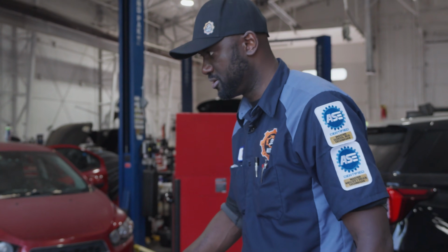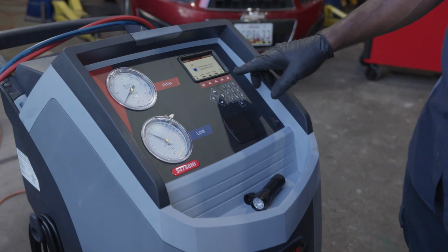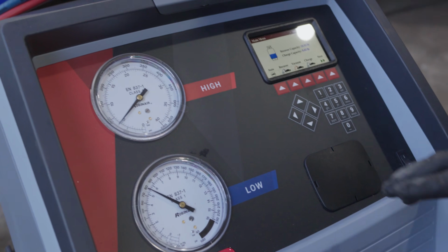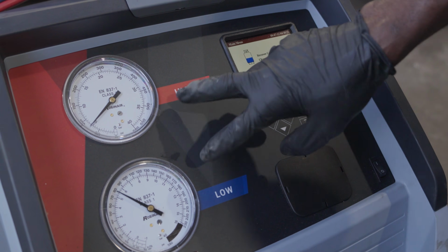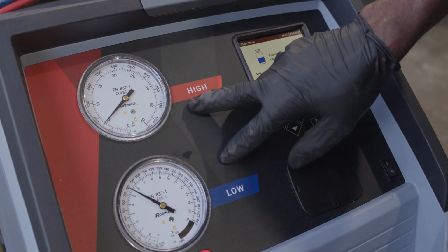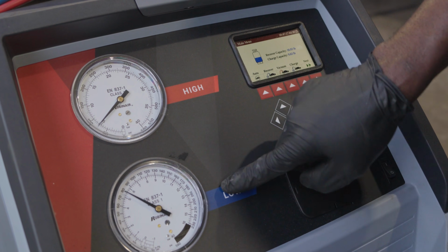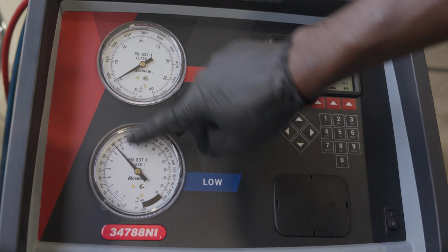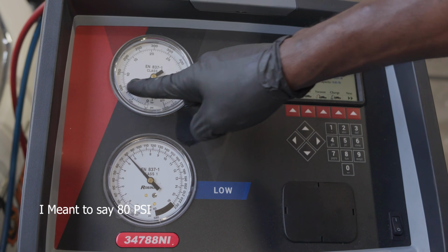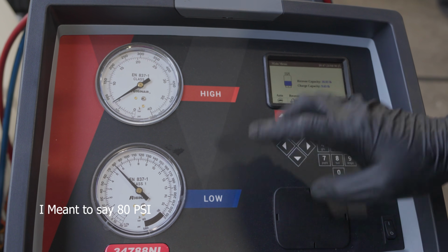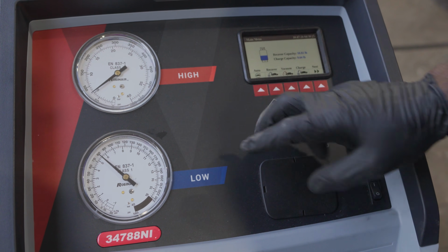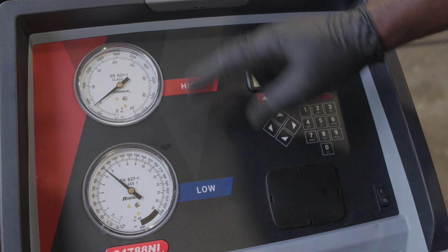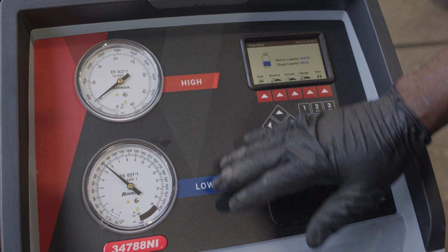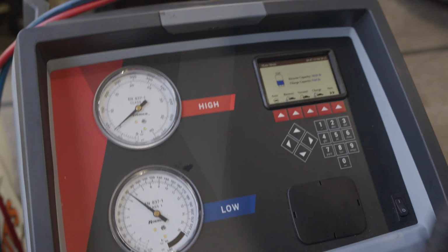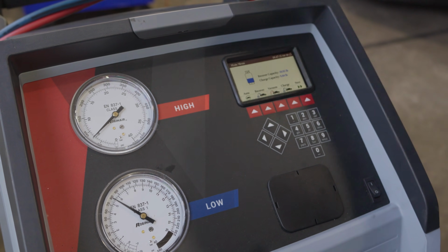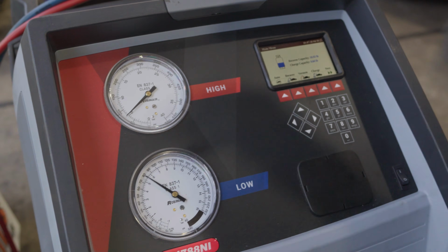Cameraman Kyler, if you can show what I'm about to do here. The other thing you want to look at is when you connect your service lines to the system, both sides have to show the same pressure. You see we're showing about 80 PSI on the low side and also 80 PSI on the high side, so that's good, because when the system is off, you should have the same pressure on both sides. This shows me there is not a restriction in the system, because if you had a restriction, one side would be higher than the other.